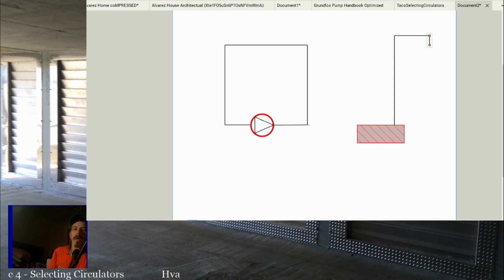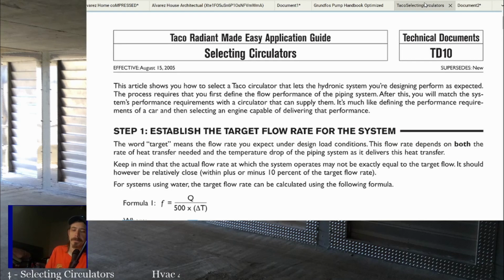Okay. So with a circulator, the feet of head is actually the friction of the piping. Okay. So if you need to find a condensate pump that can pump up 30 feet, you're going to look for a condensate pump that can handle 30 feet of head. If you need a sump pump for your basement and you need to pump that water up 10 feet, then you need a pump that can handle 10 feet of head out of that pump. All right. But when you're talking about a circulator, the feet of head isn't how high it needs to pump up.